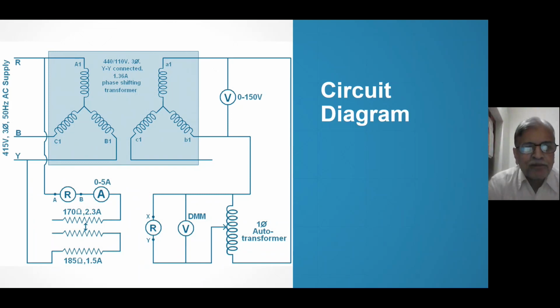Friends, this is the circuit diagram. See how many things colleges would have - I think colleges should have a phase shifter. What is a phase shifter? It's not necessary to be 440 to 110 volt, you may have 450 to 230 volt, that's not my main point. A phase shifter is a transformer, but not a simple transformer - the primary winding is stationary, but the secondary three-phase winding is rotated from 0 to 360 degrees, 0 to plus 180 degrees, and 0 to minus 180 degrees. You can rotate a voltage vector or a current vector - that is the meaning of a phase shifter.